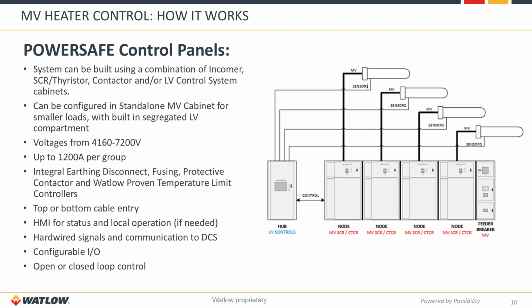There are hardwired signals that go back and forth to the DCS, as well as communication like Modbus TCP that goes back to the DCS as well for status of everything that is happening within the cabinet itself. Very configurable I/O for any types of commands or statuses you might have for the cabinet itself.